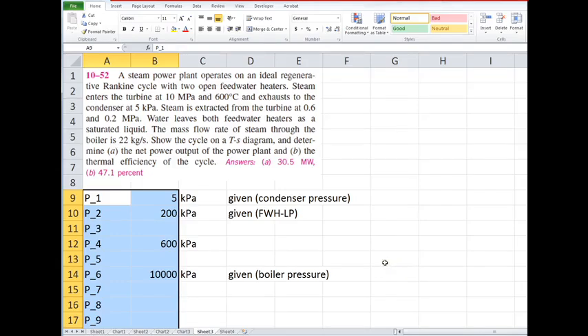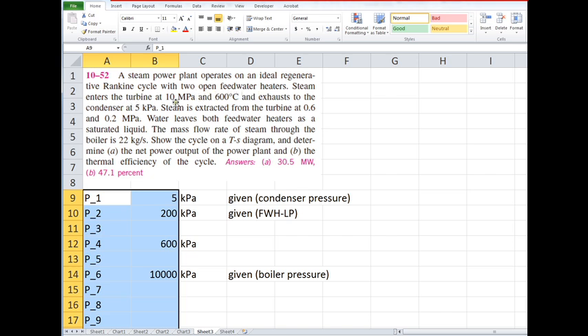Okay, let's get going and see if we can work this last example. It's a steam power plant regenerative Rankine cycle with two open feedwater heaters. Steam enters the turbine at 10,000 kPa, exhausts to the condenser at 5 kPa, but there's extraction at both 600 kPa and 200 kPa to operate the two open feedwater heaters.